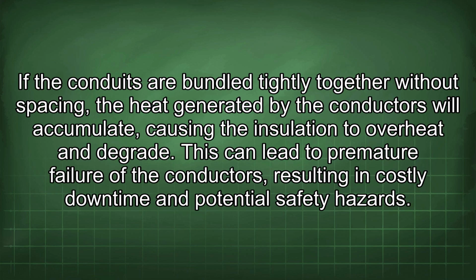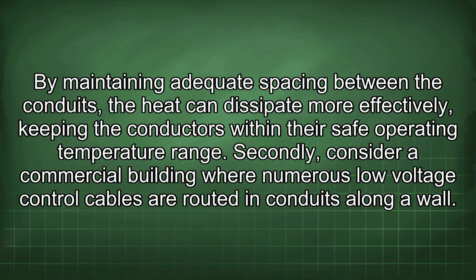If the conduits are bundled tightly together without spacing, the heat generated by the conductors will accumulate, causing the insulation to overheat and degrade. This can lead to premature failure of the conductors, resulting in costly downtime and potential safety hazards. By maintaining adequate spacing between the conduits, the heat can dissipate more effectively, keeping the conductors within their safe operating temperature range.